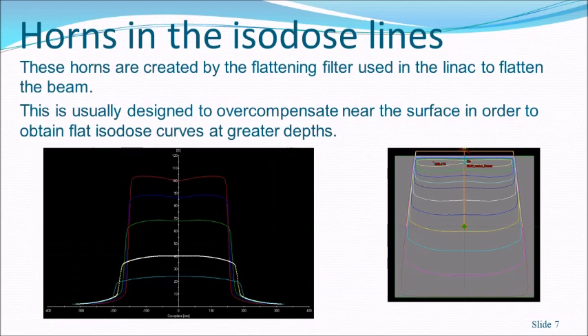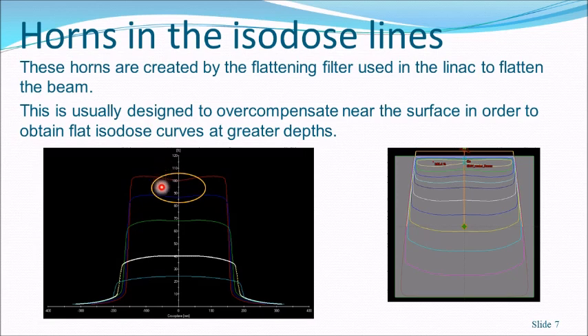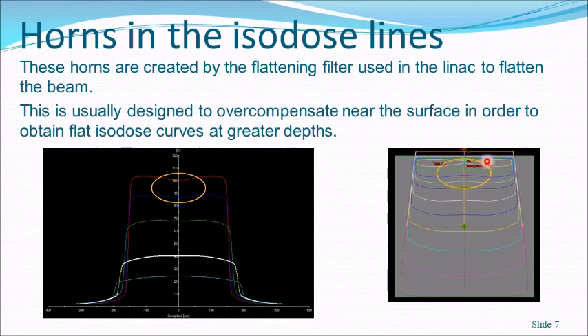When discussing beam profiles, the dose is maximum at the central axis and decreases off-axis, with the exception of horns in linear accelerators. These horns are created by the flattening filter, which is designed to overcompensate near the surface in order to obtain flat isodose curves at greater depth. At the surface, this means the central axis dose is less than the off-axis dose, creating the horns. At greater depth, the beam becomes nearly flat.